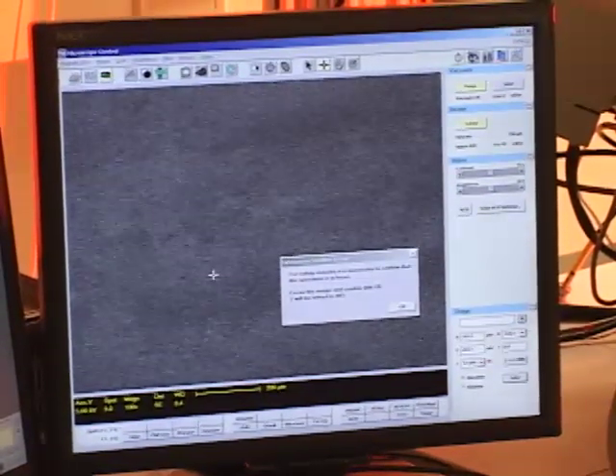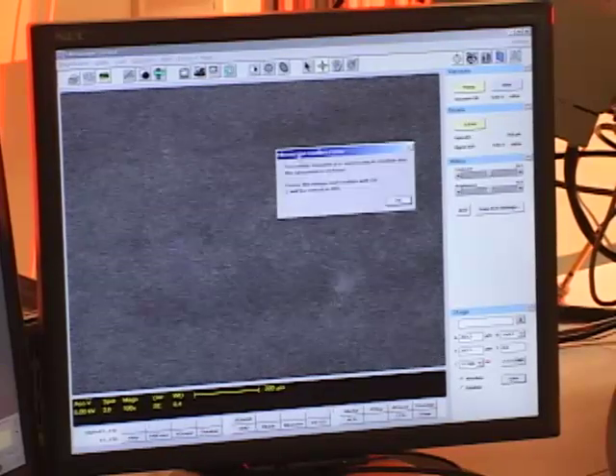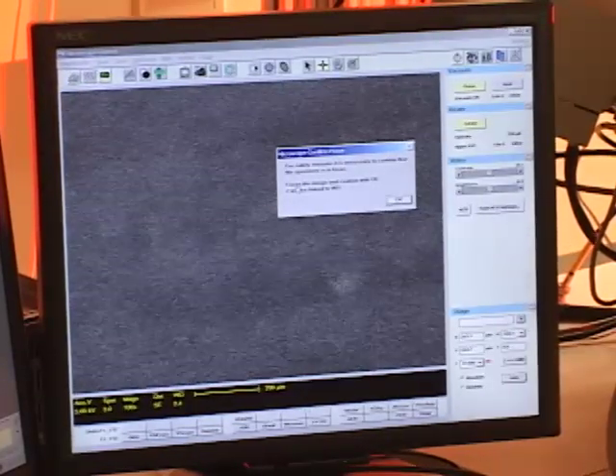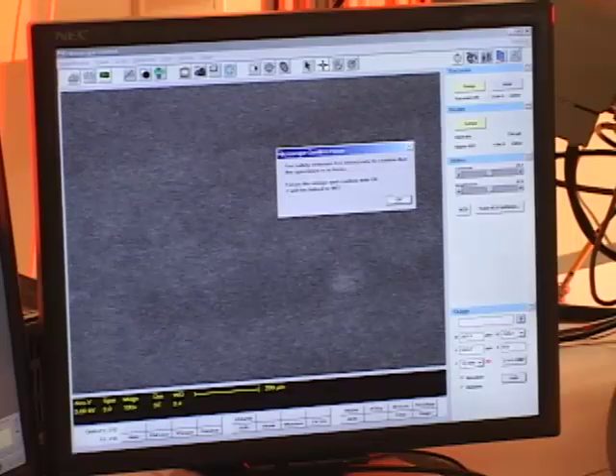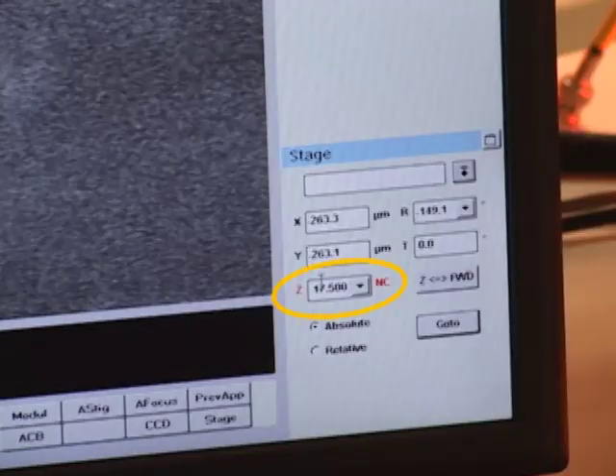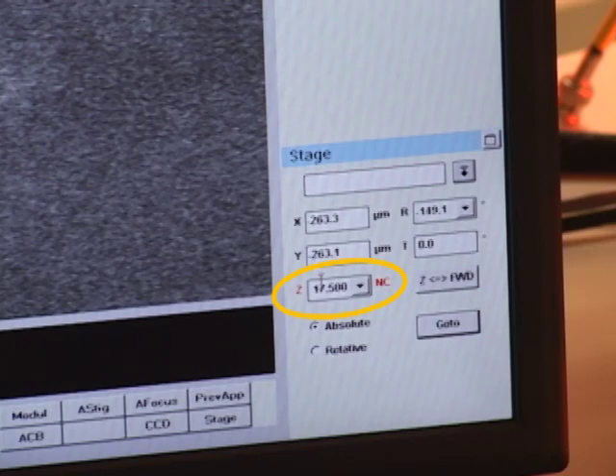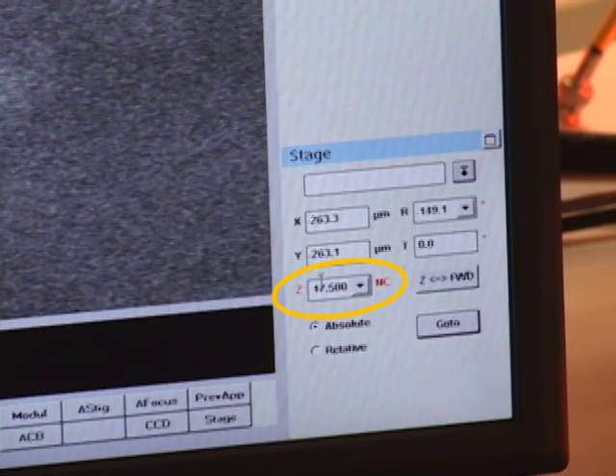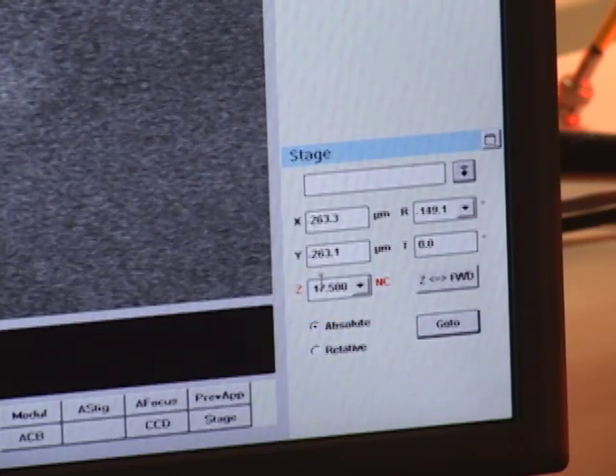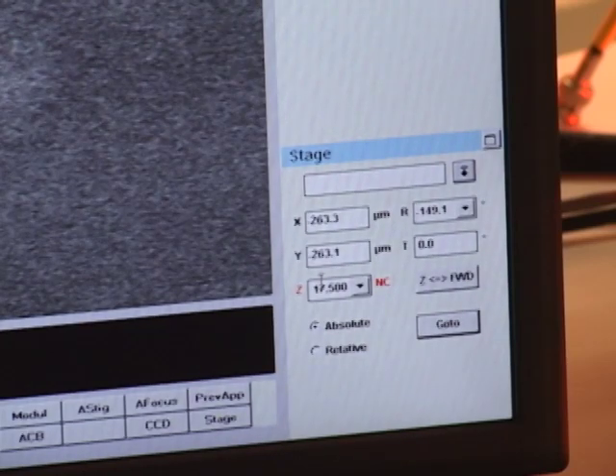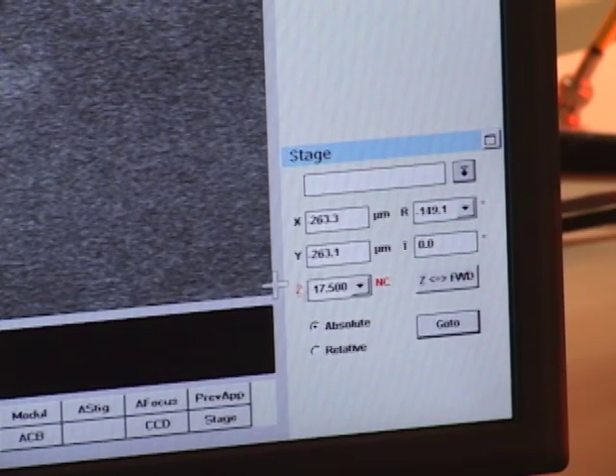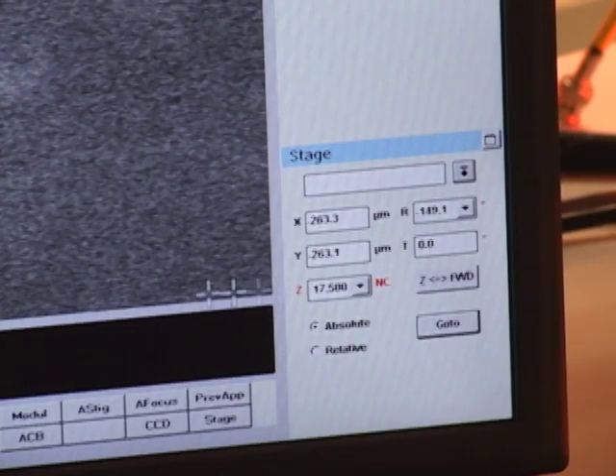So I want to confirm that the microscope is in focus at 2000x so that I can tell the microscope how much clearance we have in the Z coordinate. Right now it reads Z not calibrated and it's at a default value of 17.5 millimeters. This measurement is not a true measurement at all. When I get the sample in focus, this working distance will be a measurement in millimeters of the distance to the sample, the correct distance to the sample.